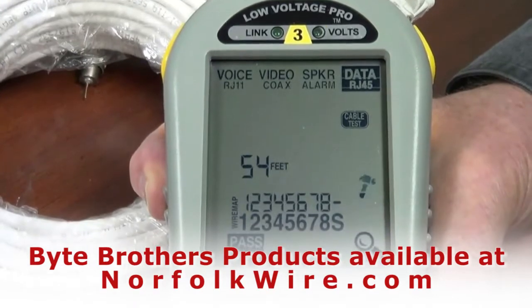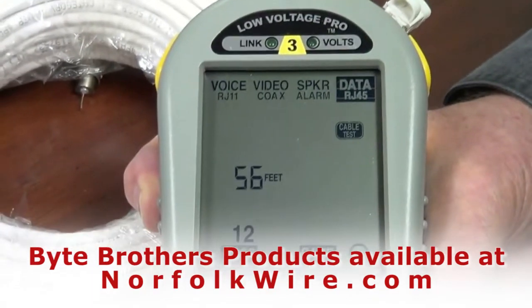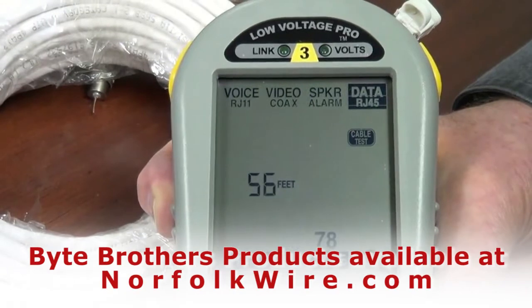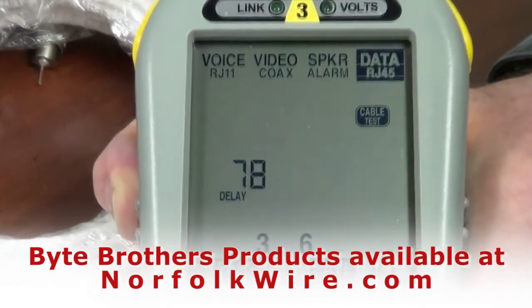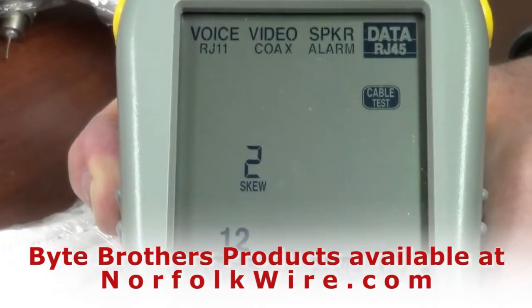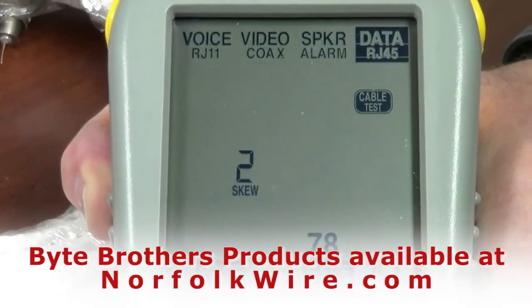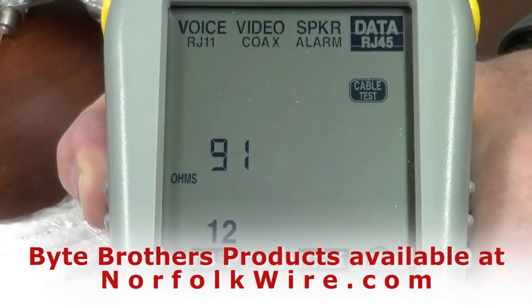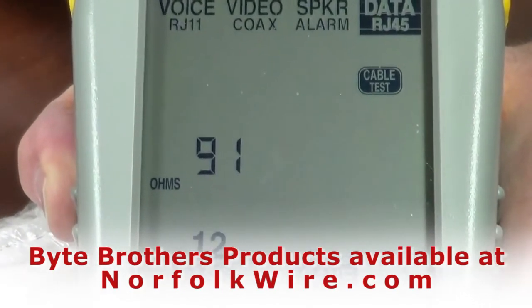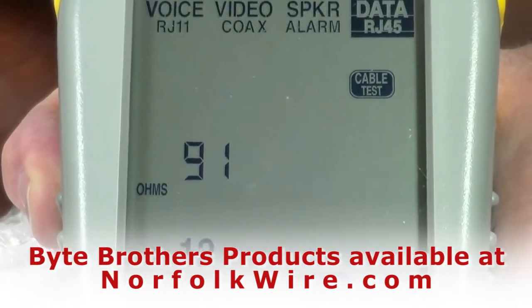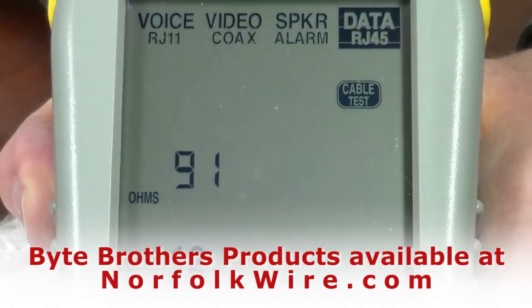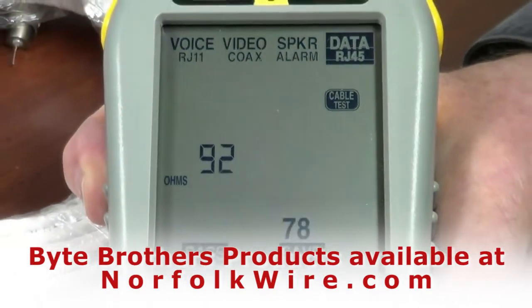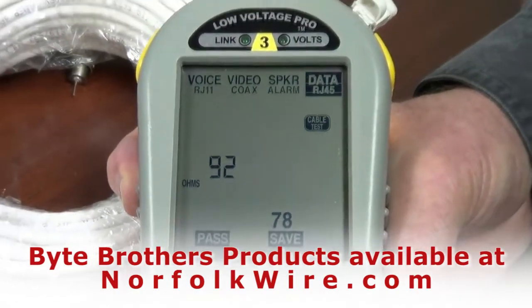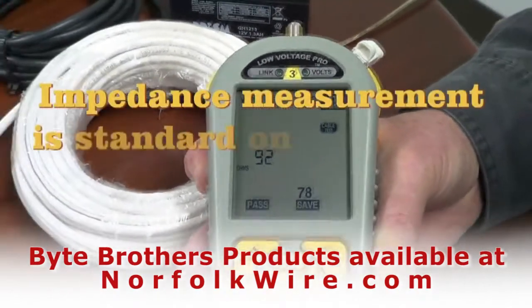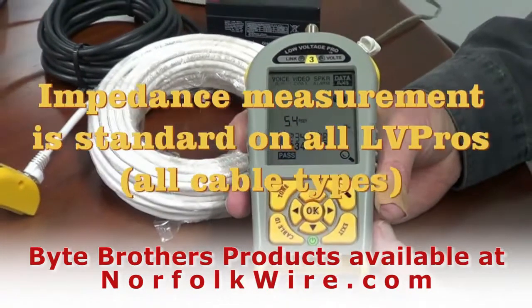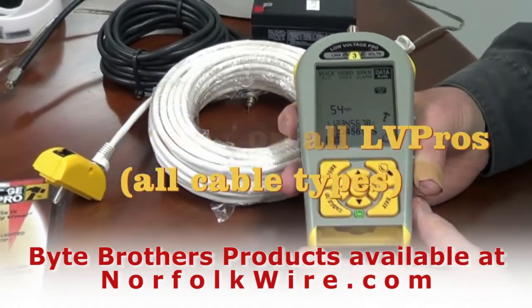I'm going to select the magnifying glass to learn more details, pushing my down arrow. I can look at my feet per pair, my propagation delay per pair, my skew per pair - all defined in the manual. And this is the impedance of the cable. Many of you know that a matching impedance cable is good for maximum data transfer, and we actually measure that. That comes standard on all models of the Low Voltage Pro, which is why we say we have an exceptional cable tester built into this.